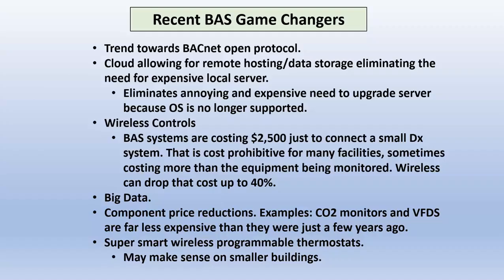Recent game changers so far as building automation systems are concerned. BACnet, and this allows, it's an open protocol, so used to be a lot of systems were proprietary, Johnson, Siemens, some still are. And basically you got locked in with them when you were stuck buying their stuff. So now we're looking more to, and ASHRAE is pushing this too, an open protocol where you can buy equipment from multiple different vendors to work in the system.